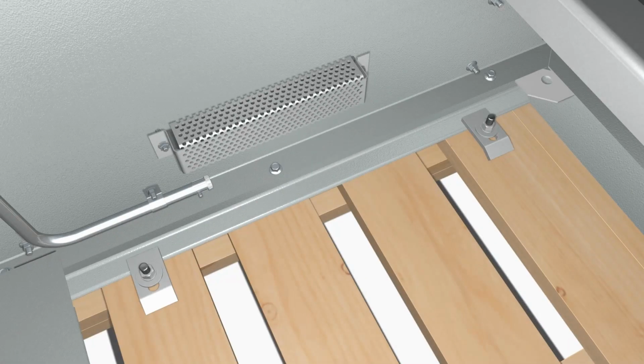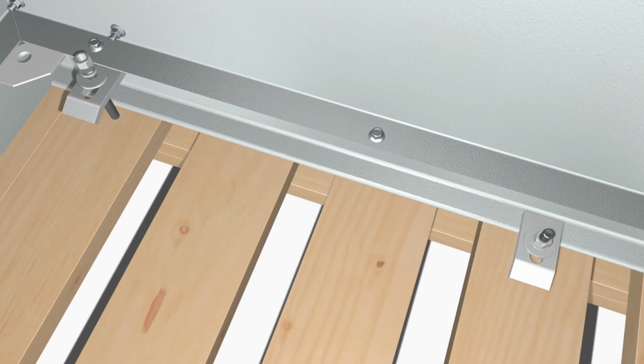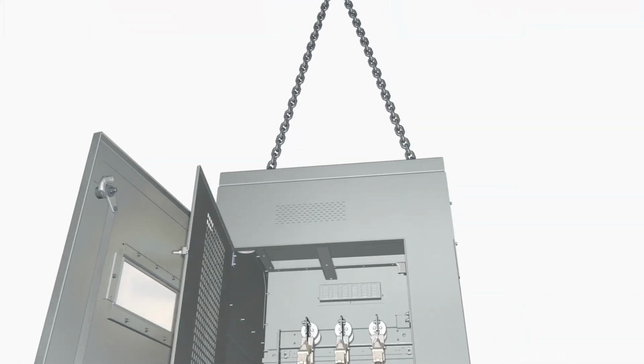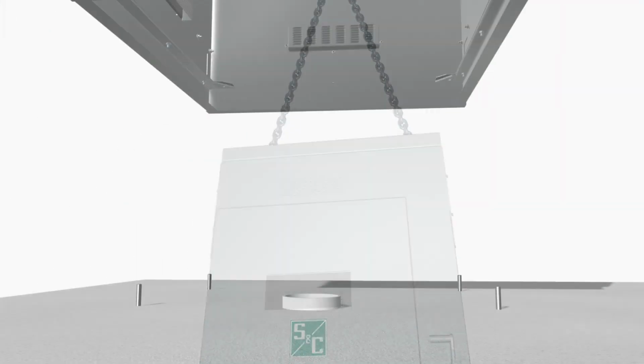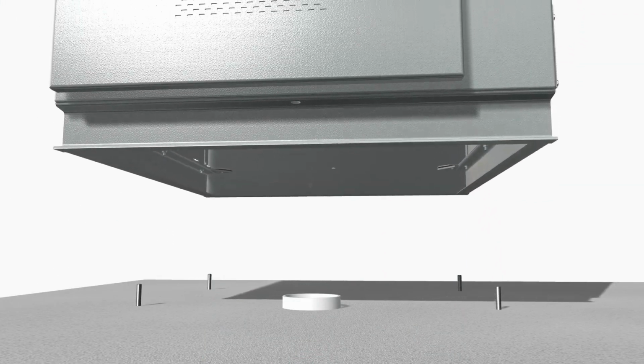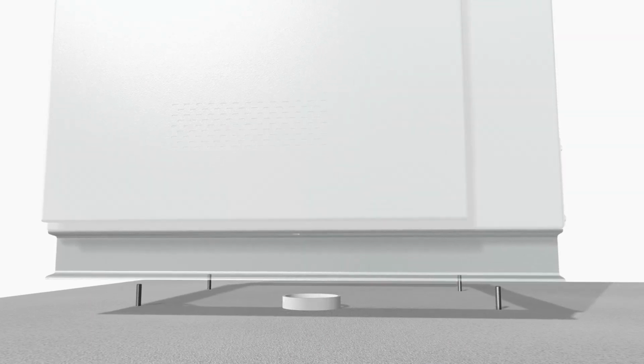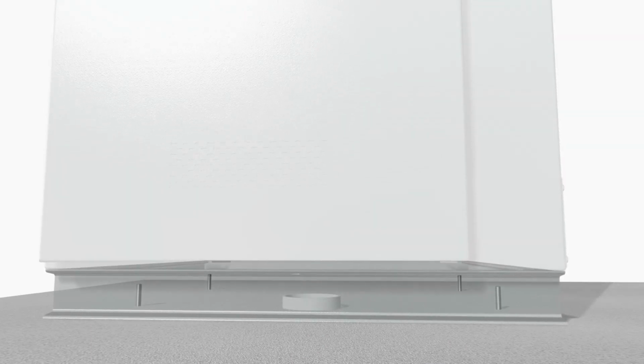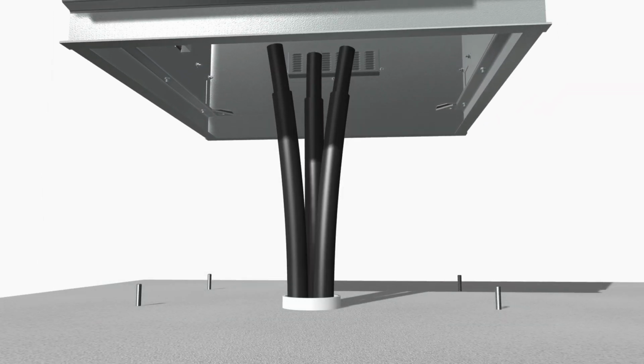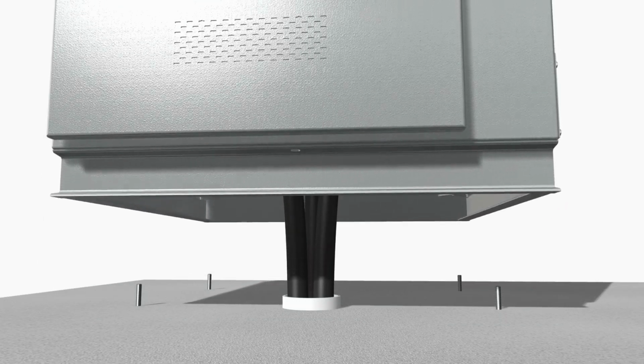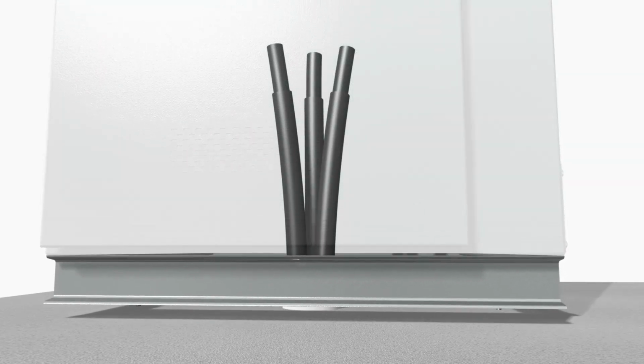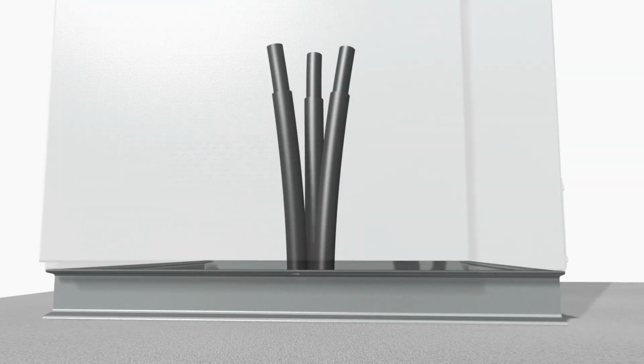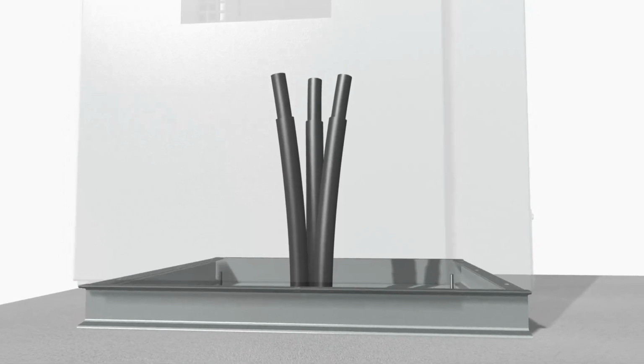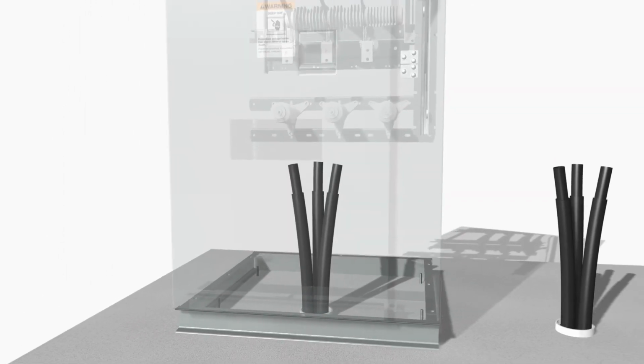A. Unbolt the unit from its skid and lift it over the anchor bolts, observing the precautions discussed earlier. B. Align the bottom of the bay so it is square with and centered on the anchor bolts. C. When power and control cables will enter the enclosure through trench or conduit in the mounting pad, check these locations for alignment with the terminating facilities provided in the switchgear.